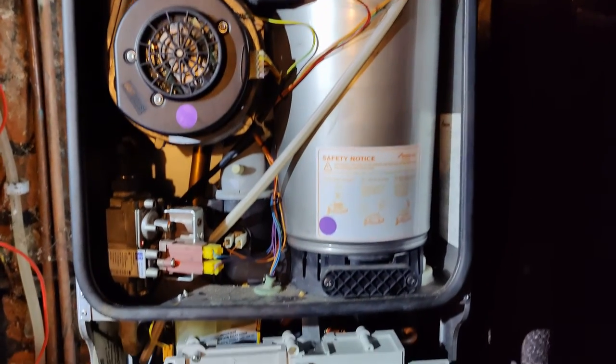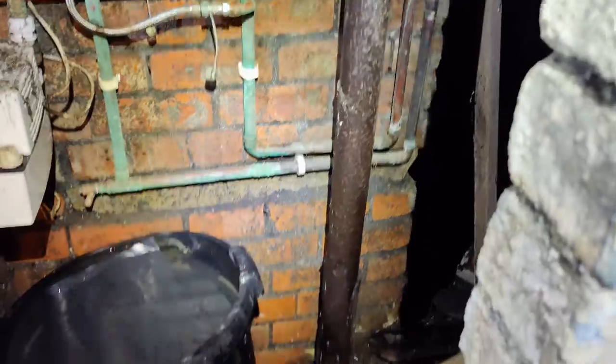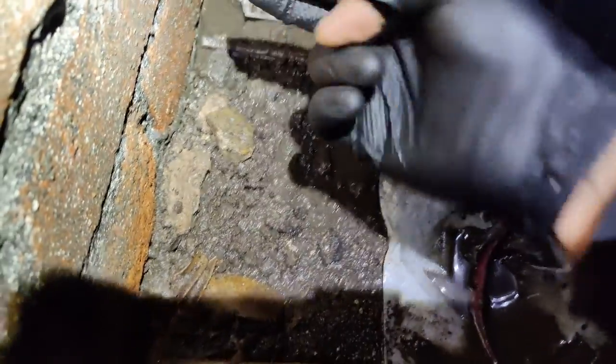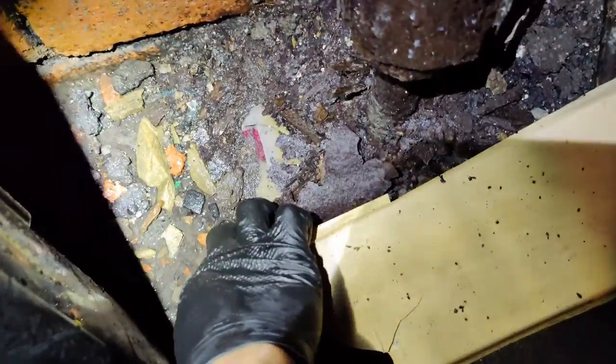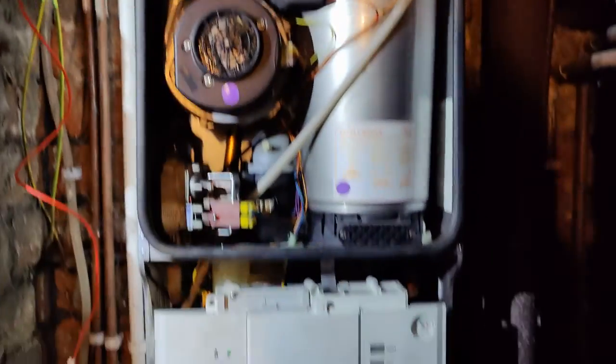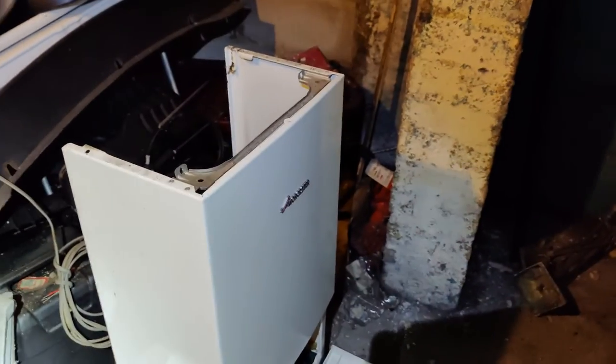Okay, so boiler's back on. Return manifold and the pump's changed, and I should have had a closer look around where somebody previously changed the flow adapter, and they decided these things that came out of the old flow adapter were not necessary and just chucked them away. And I have to buy some more. That's another one saved. I just need to find some screws for the cover, and that's all done.